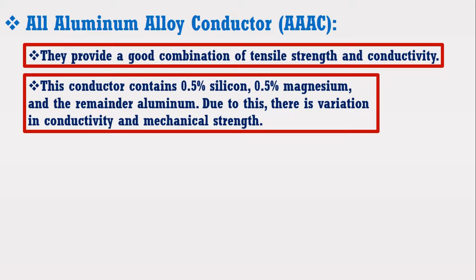Electrical conductivity is 53.5% of international annealed copper standard and ultimate tensile strength is 30 kg per millimeter square. It means that conductivity of this conductor is slightly reduced. It is because aluminium has conductivity of 61% as discussed in the previous lecture. On the other hand, tensile strength of this alloy is increased because aluminium has tensile strength of 16.21 kg per millimeter square as discussed in the previous lecture.